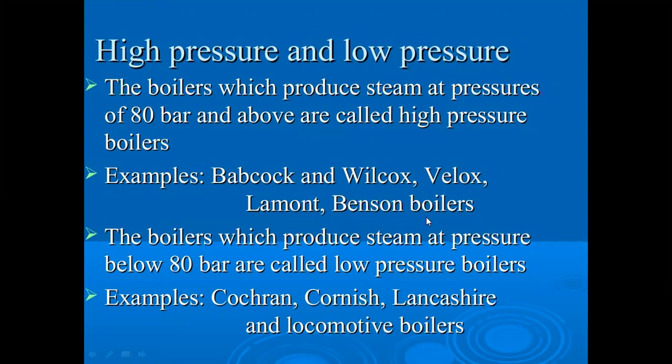In the Lamont boiler, the operating pressure is 125 bar. In the Benson boiler, the operating pressure is 210 bar. It is more than 80 bar, so these are all high pressure boilers. These high pressure boilers are also called modern boilers. The boilers which produce steam at a pressure below 80 bar are called low pressure boilers.